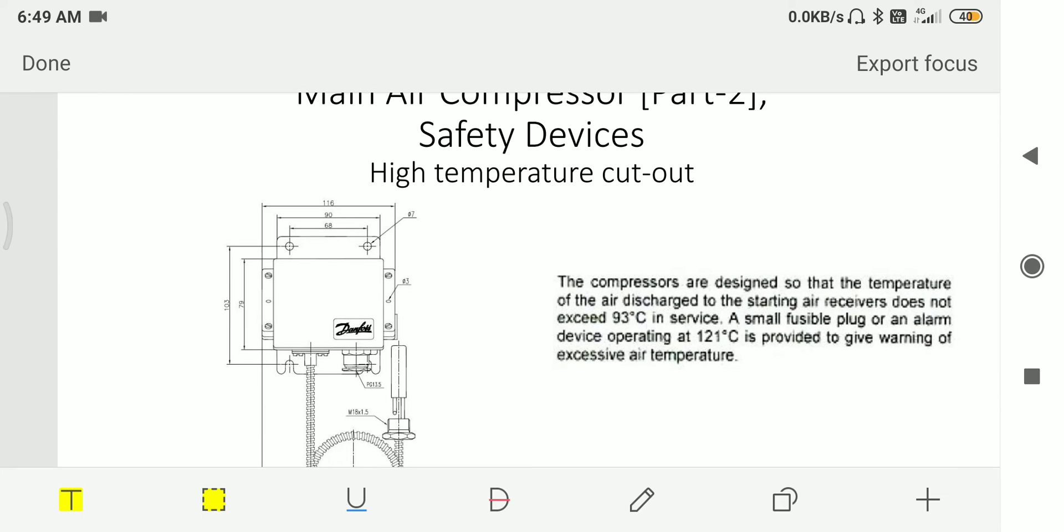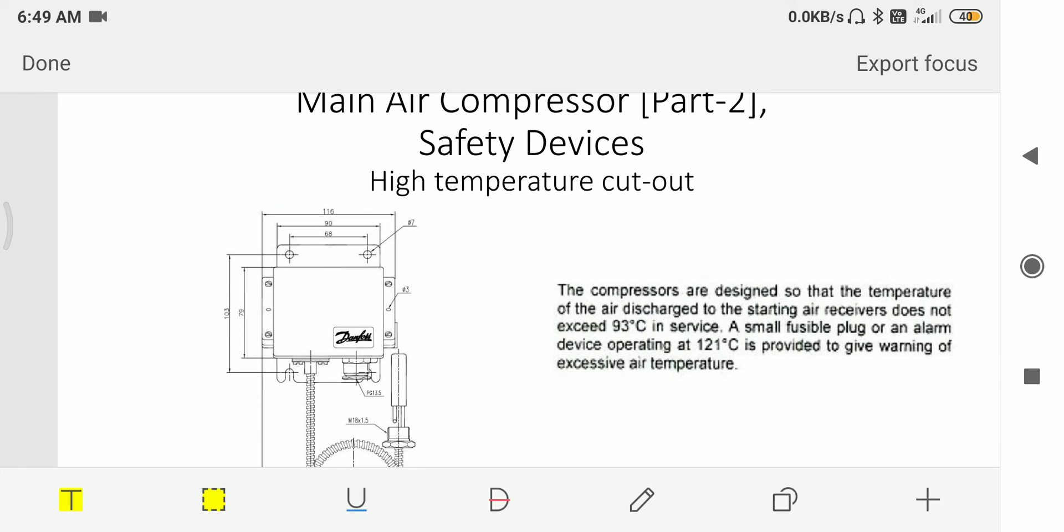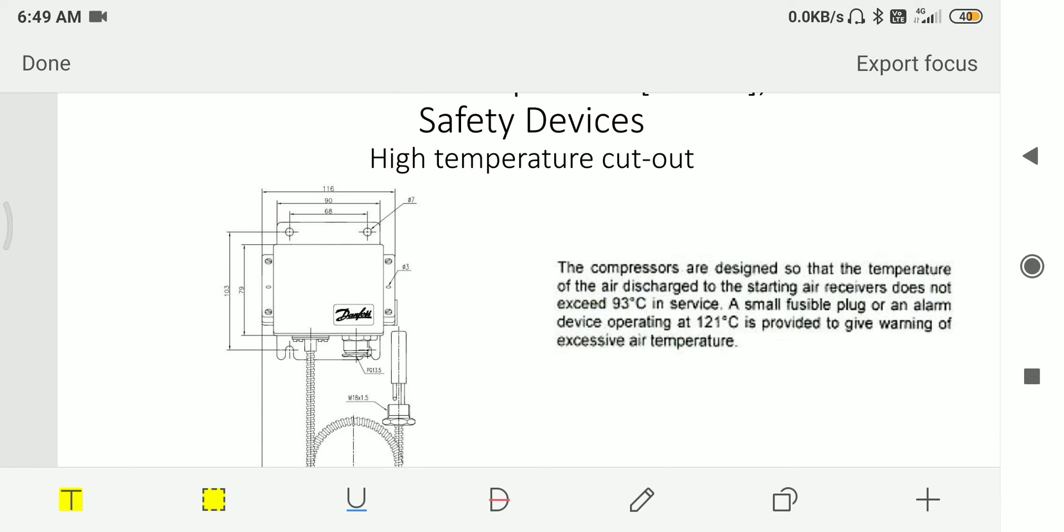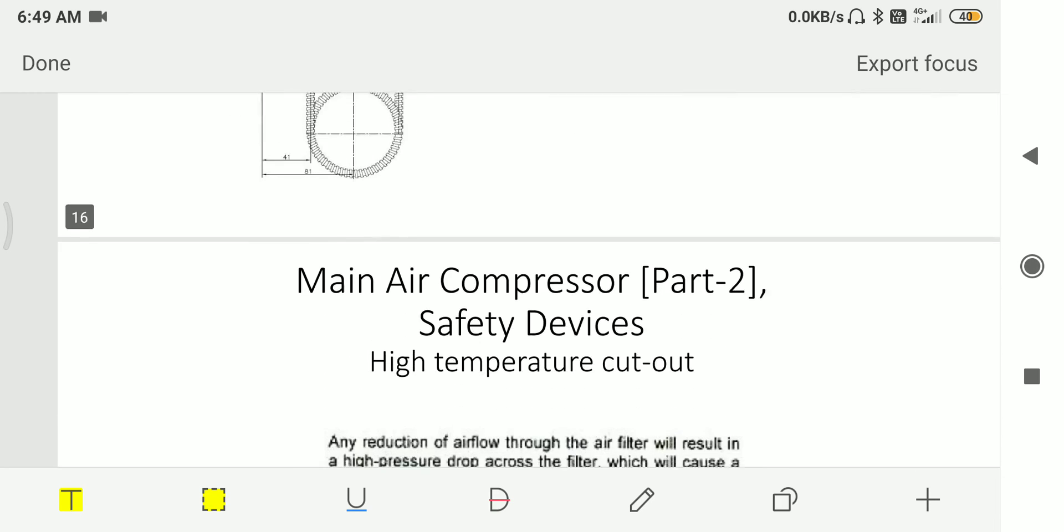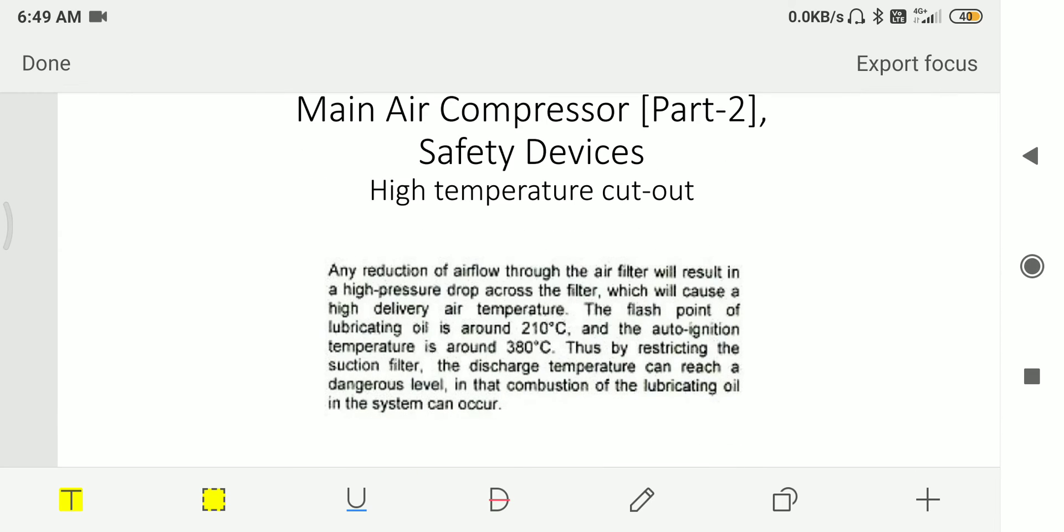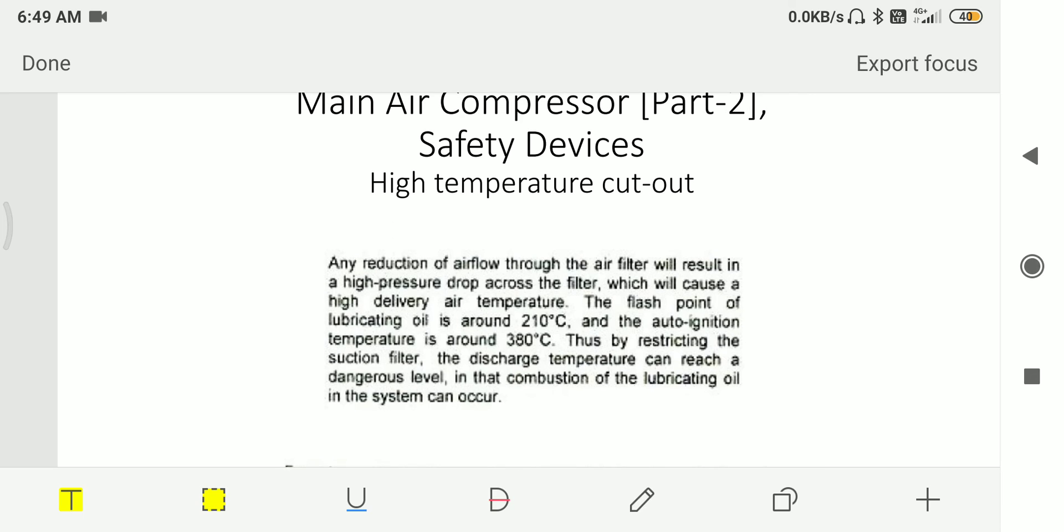Then we have high temperature cutout. The compressors are designed so that the temperature of the air discharged to the starting air receiver does not exceed 93 degrees Celsius in service. A small fusible plug or an alarm device operating at 121 degrees Celsius is provided to give warning of excessive air temperature.